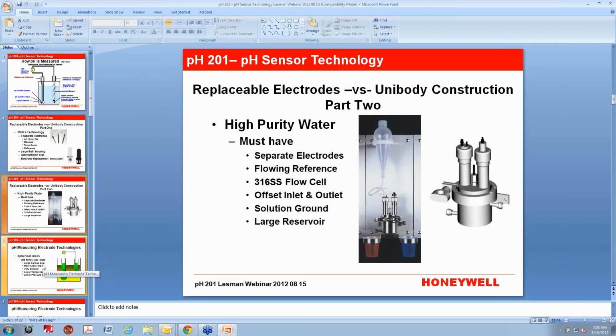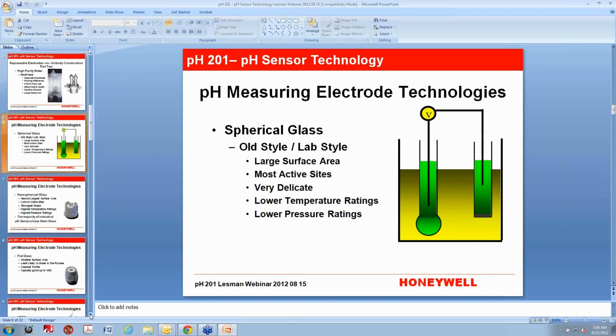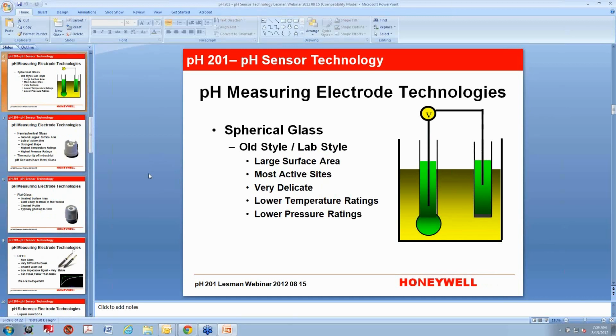So if we go down and have a look at measuring electrode technologies, I'm going to go oldest to newest. These are all out there. A lot of people are still making spherical glass, which means it's basically a ball of glass on top of a small Pyrex stem, a cheap, inexpensive glass stem. So the active sites on the measuring electrode are on that ball. It has an extremely large surface area, which is nice because the surface area relates to how long the sensor lasts in terms of how many active sites you have that the hydrogen ions can land on. So it has the largest surface area, and therefore the most active sites.